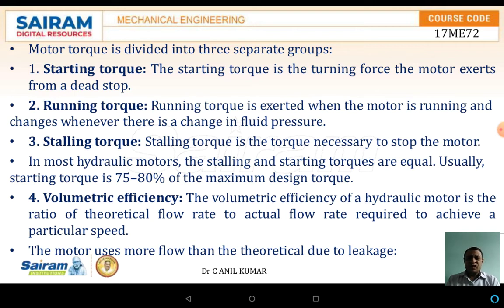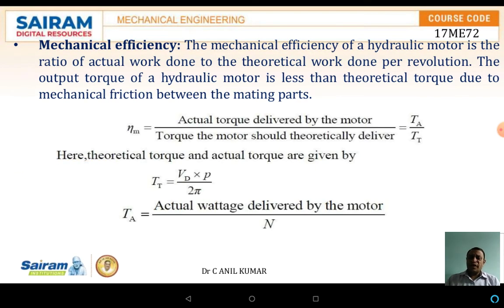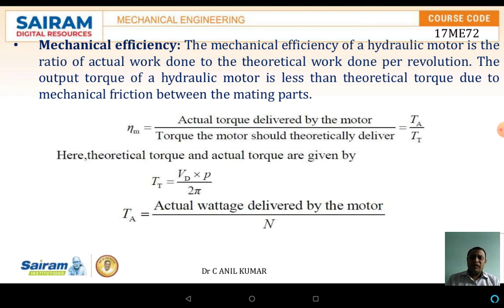The volumetric efficiency of the hydraulic motor is the ratio of the theoretical flow rate to the actual flow rate required to achieve a particular speed. The mechanical efficiency of the hydraulic motor is the ratio of the actual torque delivered by the motor to the theoretical torque delivery. Normally, the output torque of the hydraulic motor is less than the theoretical torque due to mechanical friction between the mating parts.